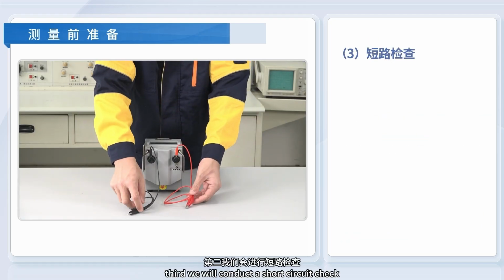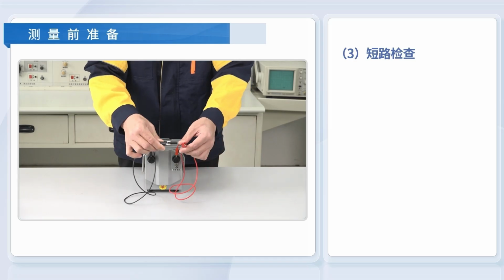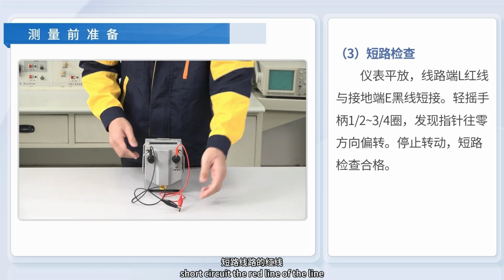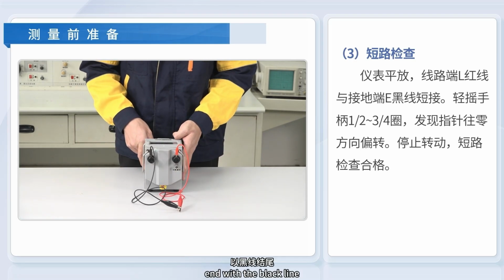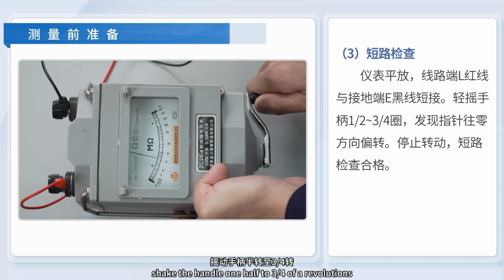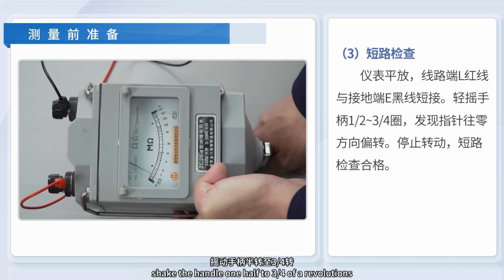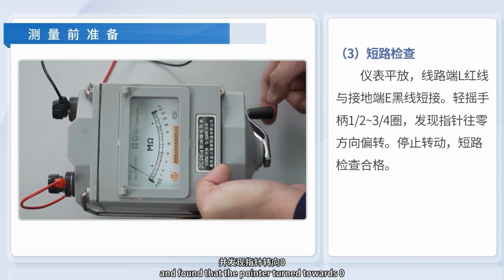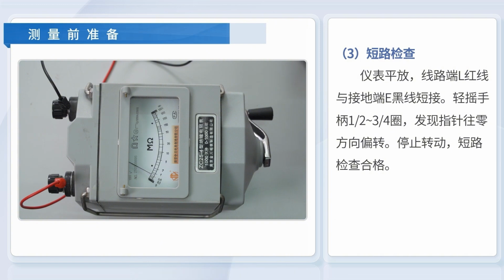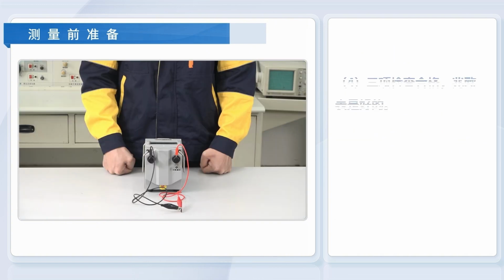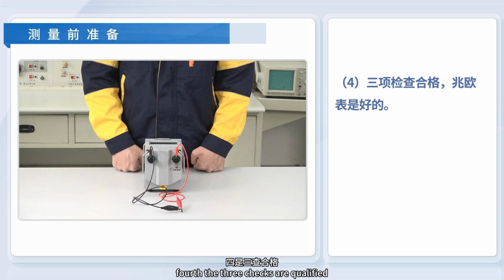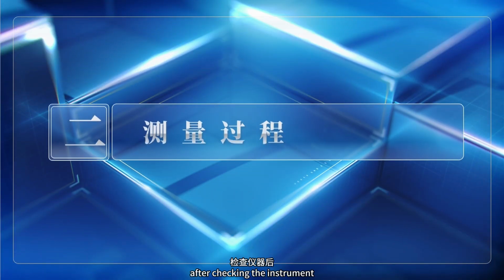Third, we will conduct a short circuit check. Place the instrument flat. Short circuit the red line of the line end with the black line. Shake the handle 1/2 to 3/4 of a revolution, and the pointer turns towards 0 and stops rotating. The short circuit test is qualified. Fourth, the 3 checks are qualified. The megohmmeter is good. After checking the instrument, we start to measure the insulation resistance of the motor.